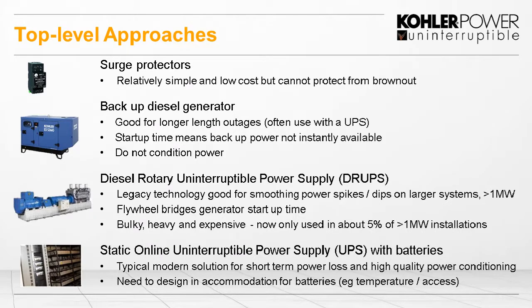The most common form of conditioning is to use a static online UPS coupled with its batteries. And these provide typically short-term protection against power loss and always online, giving high-quality power conditioning. But there are some needs that we have to accommodate with static UPSs, and we go into some of that with temperatures and access for when we install these into the buildings.